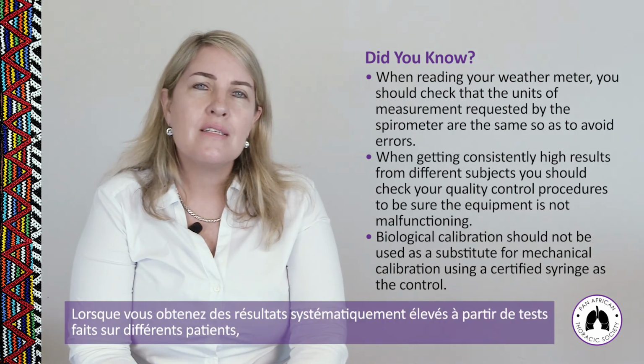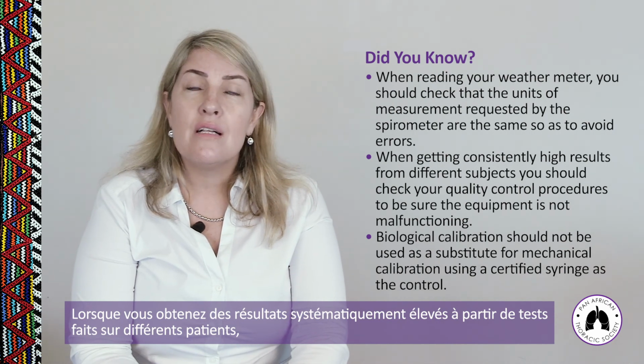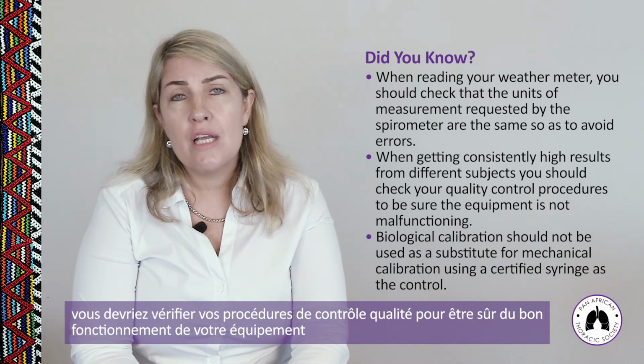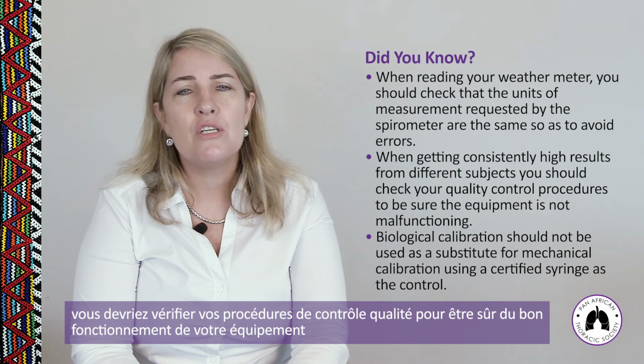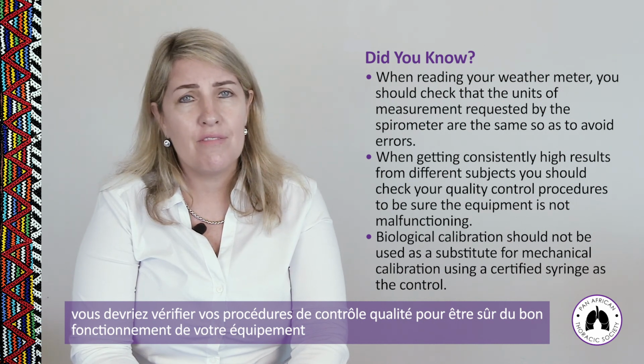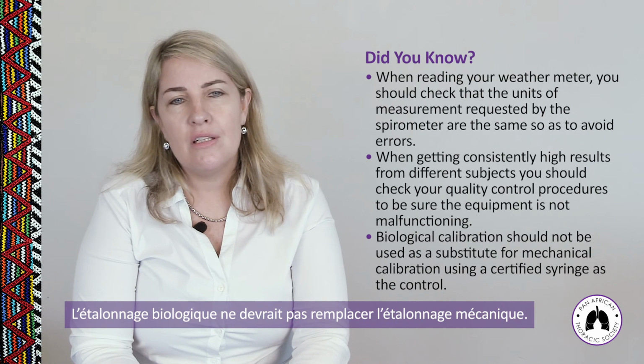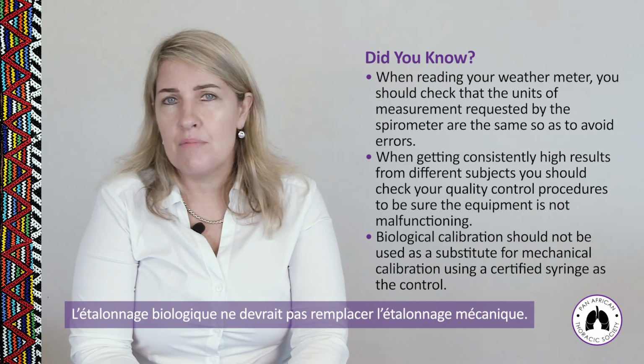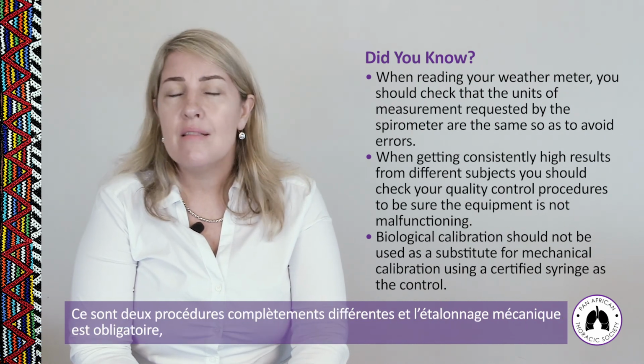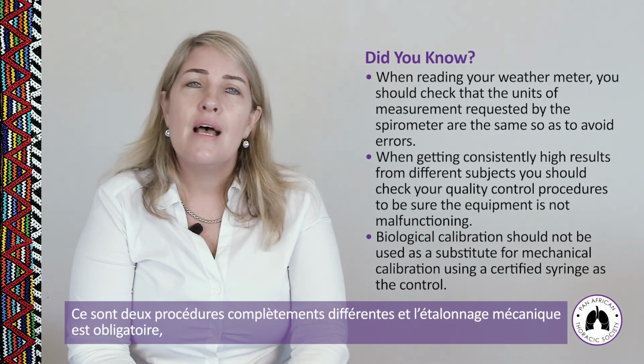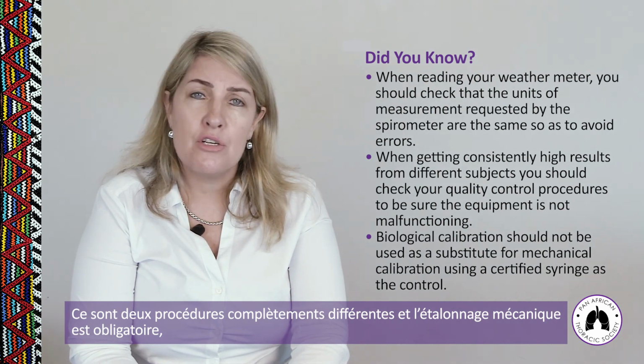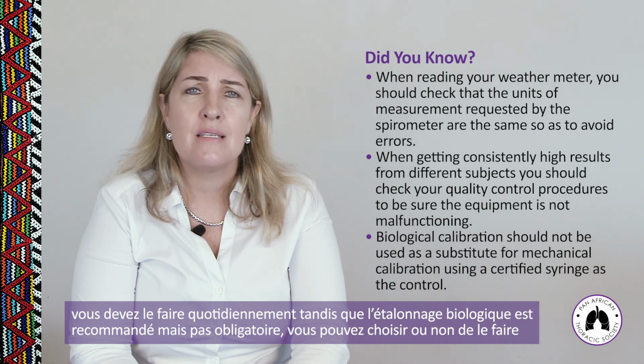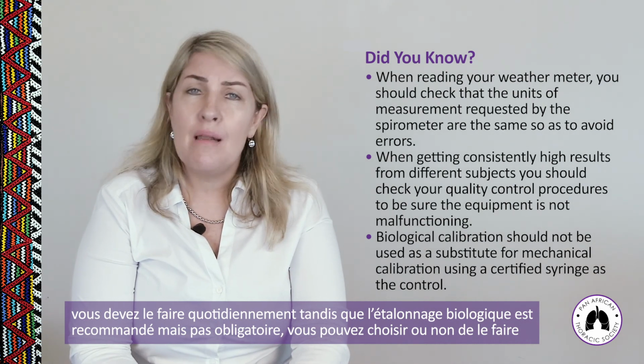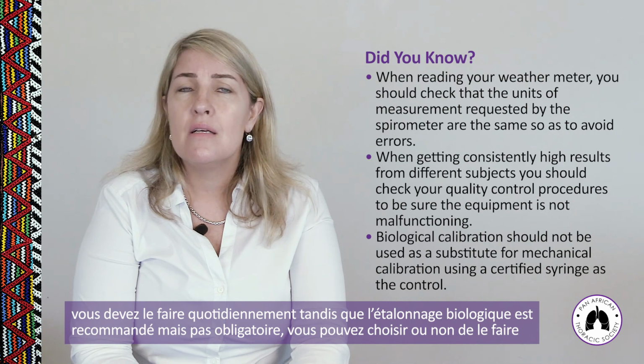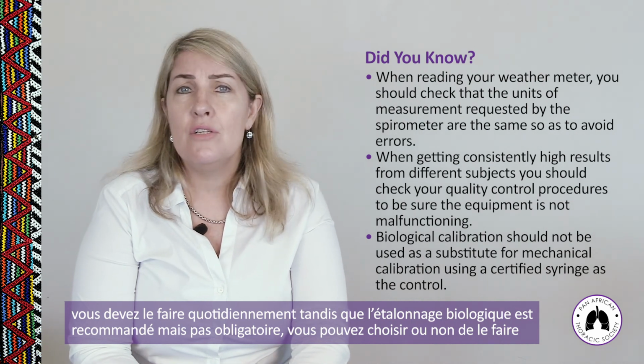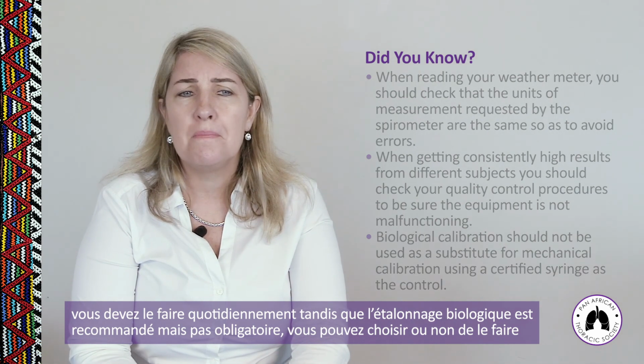When you are getting consistently high results from different subjects, you should check your quality control procedures to be sure that the equipment is not malfunctioning. Biological calibration should not be used as a substitute for mechanical calibration. They are entirely different procedures. A mechanical calibration is mandatory. You have to do it on a daily basis, whereas a biological calibration procedure is recommended, but it is not mandated. You can choose whether you want to do it or not.